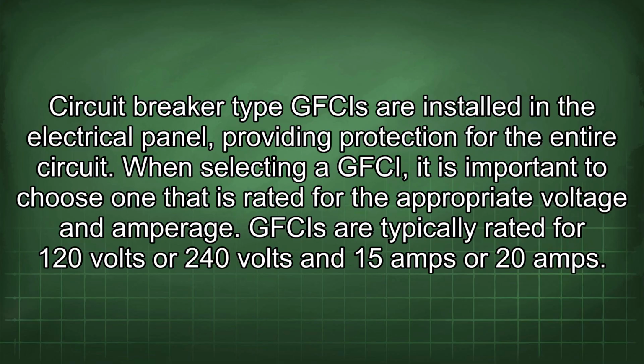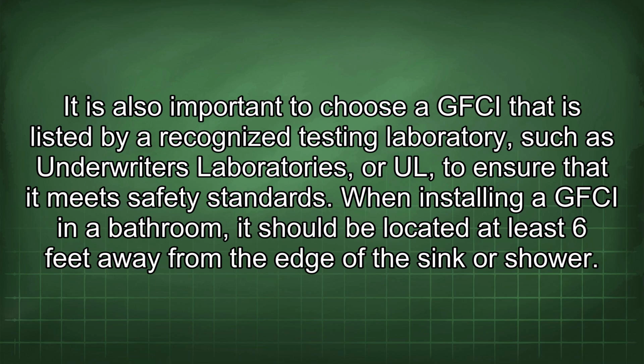GFCIs are typically rated for 120 volts or 240 volts and 15 amps or 20 amps. It is also important to choose a GFCI that is listed by a recognized testing laboratory, such as Underwriters Laboratories, or UL, to ensure that it meets safety standards.